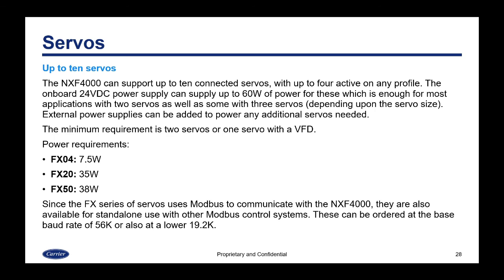The power requirements for the servos for the FX04 is 7.5 watts, the FX20 is 35 watts, and the FX50 is 38 watts. Since the FX series of servos uses Modbus to communicate with the NXF4000, they are also available for standalone use with other Modbus control systems, such as a PLC. These can be ordered at the base baud rate of 56K as well as a lower baud rate of 19.2K.